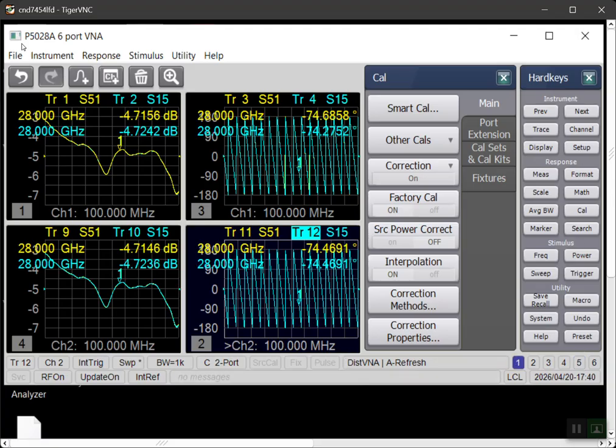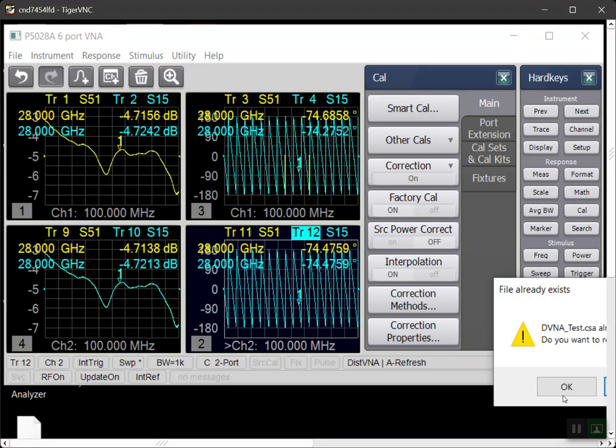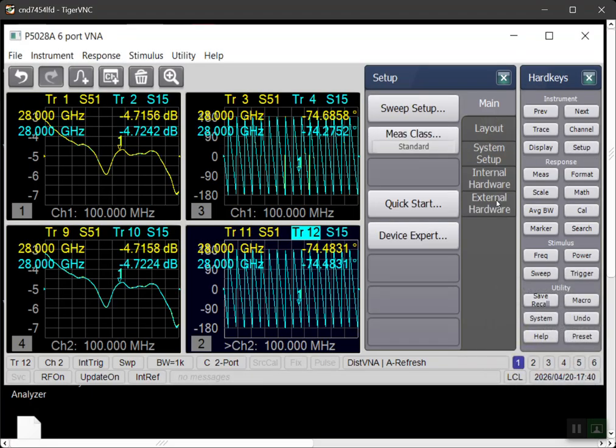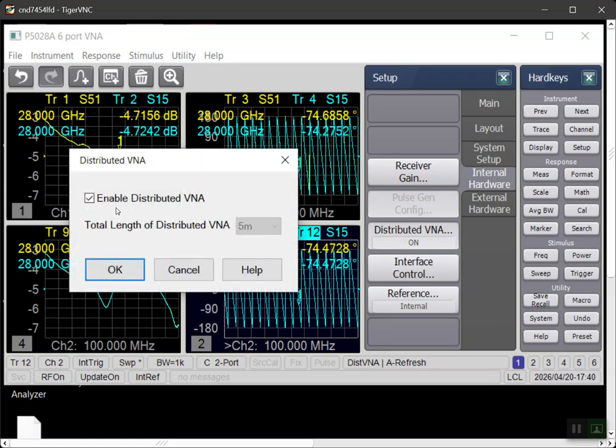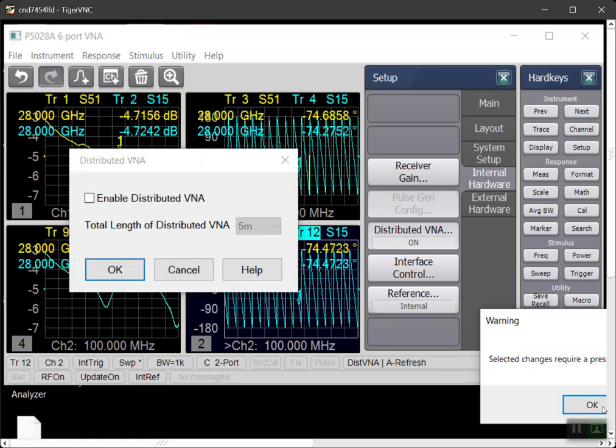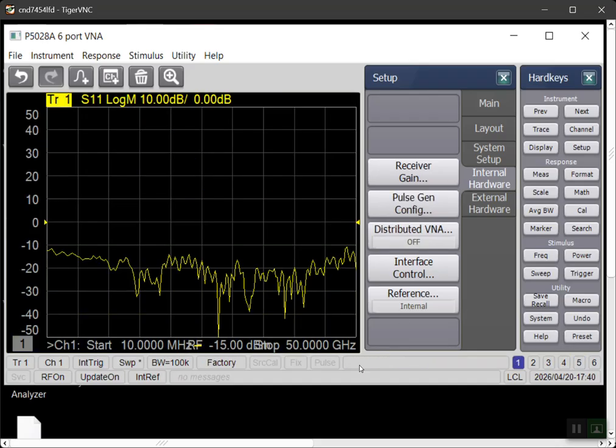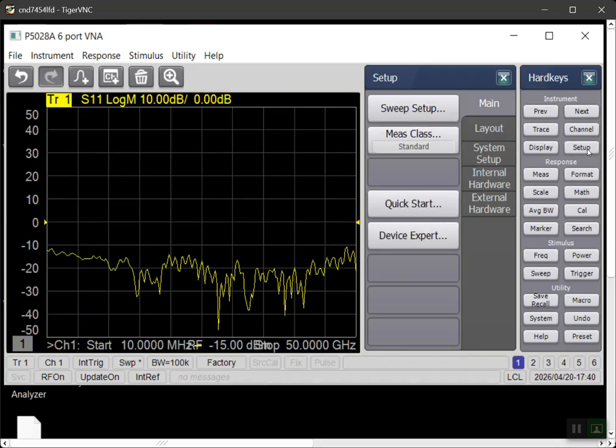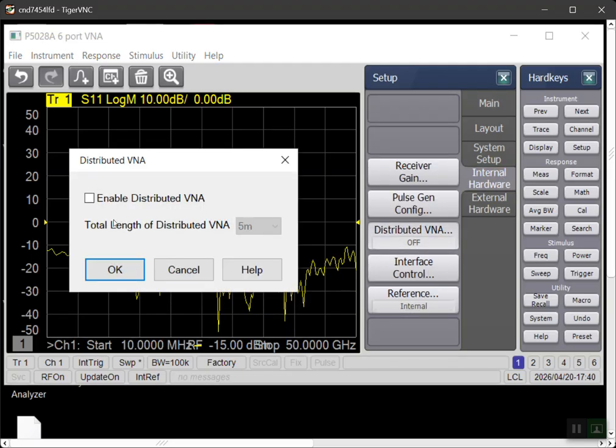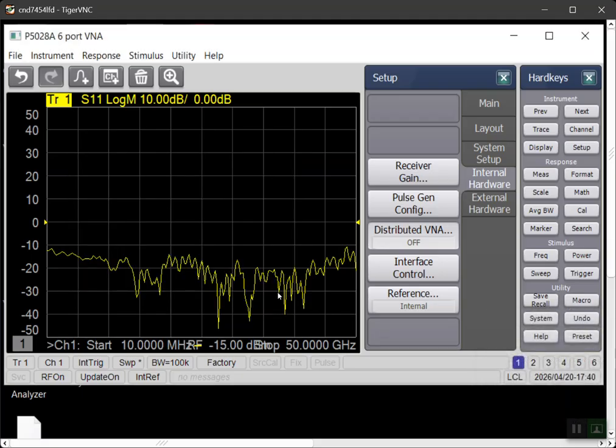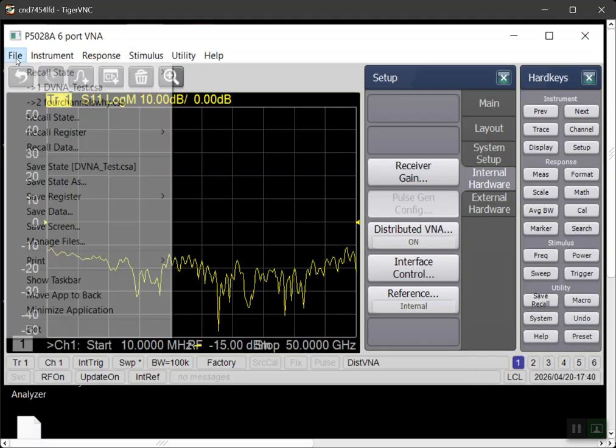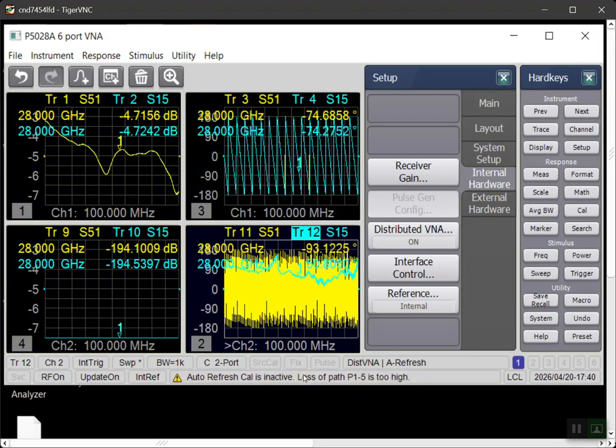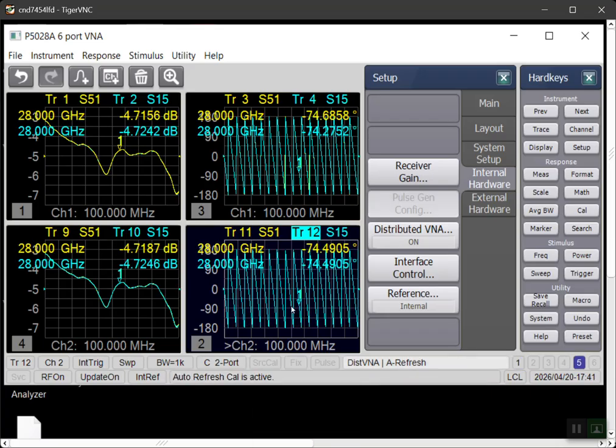Let me save the state, distributed VNA. It's just set up under internal hardware, to see if you want to be in the mode or not. Let's turn it off. So if you've preset in normal mode, this is what it comes up. But if you want to go in distributed VNA, you say setup, internal hardware, distributed VNA on. And right now, the only length it officially supports is 5 meters. I mean, we have a longer cable, but it's okay. And then now I'm in this mode and I can recall my state and everything else kind of operates normally. So that's it. It takes a minute and then it applies it.